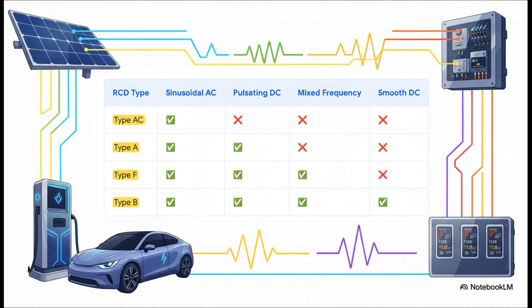Power supplies in our computers and TVs create pulsating DC fault currents. Variable speed drives, they can spit out mixed high-frequency faults. And things like solar inverters or EV chargers can produce smooth DC fault currents. A Type AC RCD is completely blind to all of that, which means it just won't trip when it's supposed to. And that is why we have Type A, Type F, and Type B RCDs. Each one is engineered to see a wider, more complex range of these modern fault types.